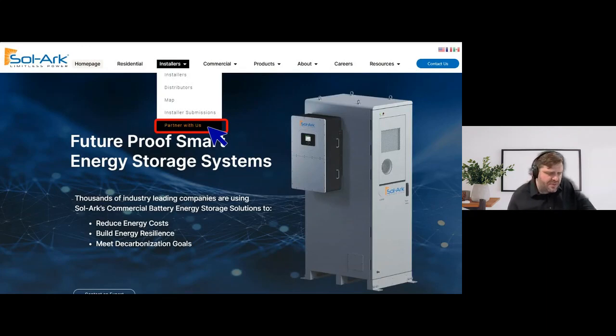And so with large battery banks, the design challenge is you need to have a bus bar, and before you land on the bus bar, you need to fuse the conductors coming out. Generally, far less than the output rating of what the battery would otherwise regulate.